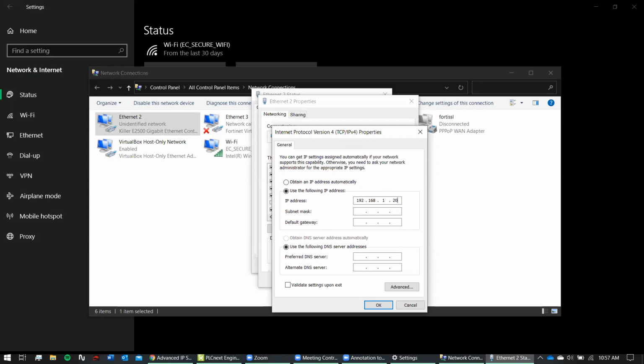Depending on your network size, that may be used. Since we're just connecting to one PLC and one Profinet module, we know that should be open. When you click on the subnet mask, it will automatically populate. For the default gateway, you can leave this as all zeros, or you can fill it in with 192.168.1.1, which would just be the first default gateway if you had a setup like this. If you're plugged into a router, your default gateway is your router's IP address, which is usually the first address in that subnet.